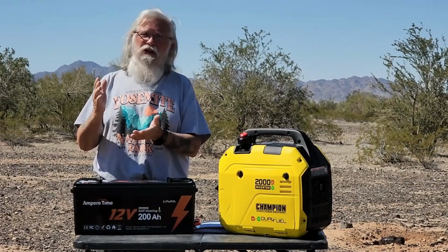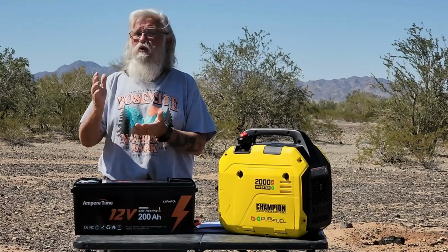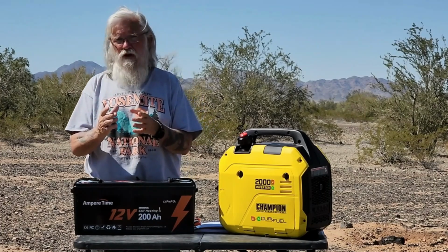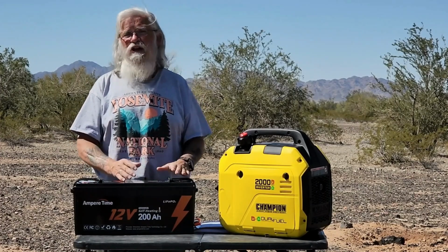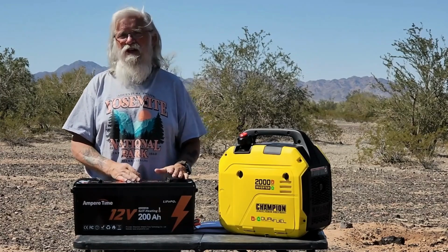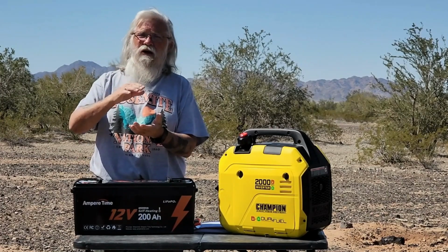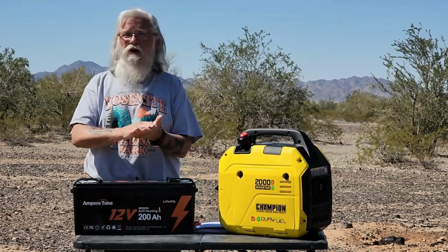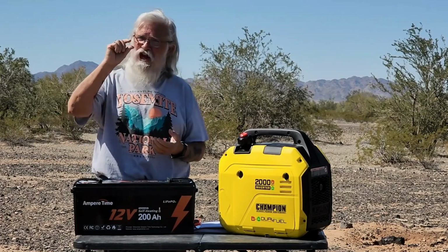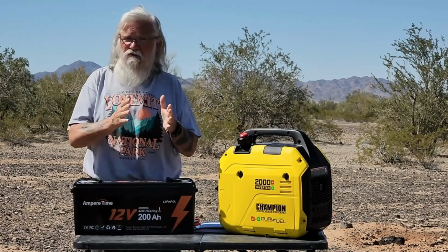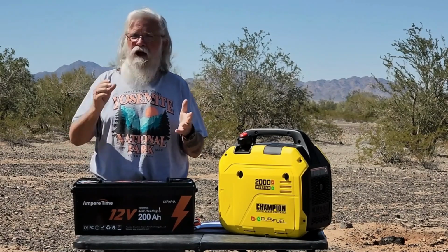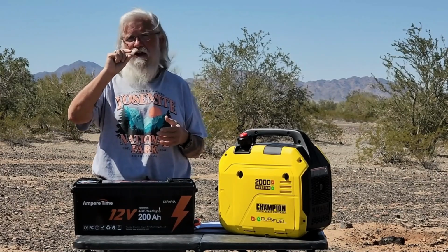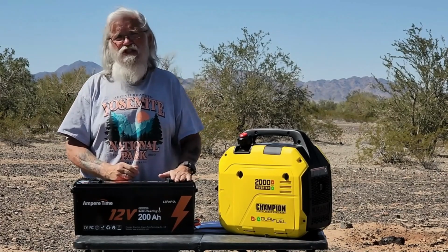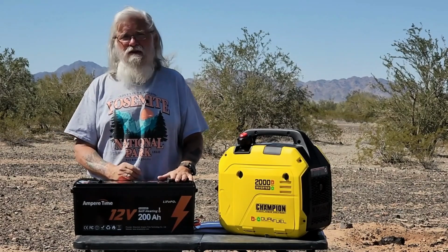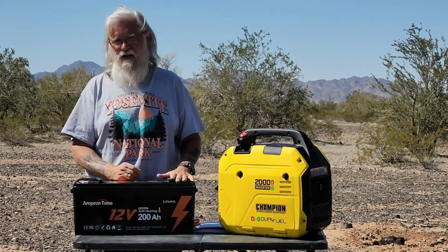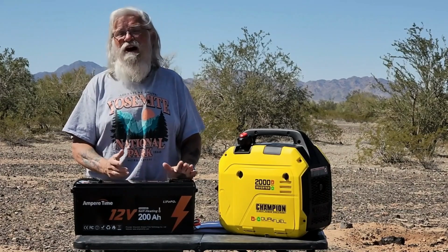But if you only take it down 20%, from 100% to 80% full, they're saying this will get 15,000 cycles. So the shallower the cycle, the more cycles you get. Because I'm going to have a very big battery bank, mine will never be more than shallow cycling, meaning I could get 15,000 cycles out of this. That's 10 years or more easily, as opposed to 1,000 cycles.